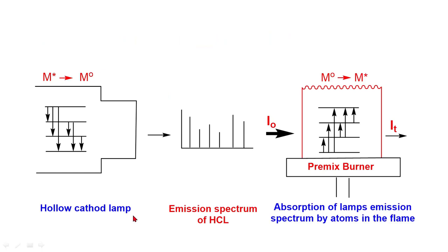This is the hollow cathode lamp where excited state atoms go to ground state and give rise to emission spectrum. This radiation is allowed to pass through the flame of premix burner. In the flame there are ground state gaseous atoms. They can absorb the characteristic radiation and go to the excited state.